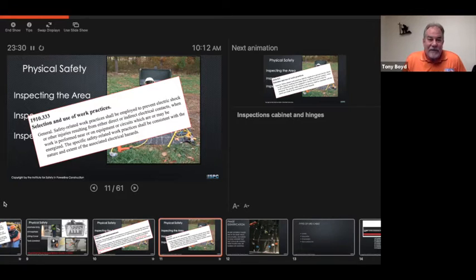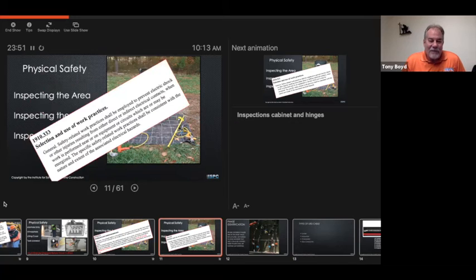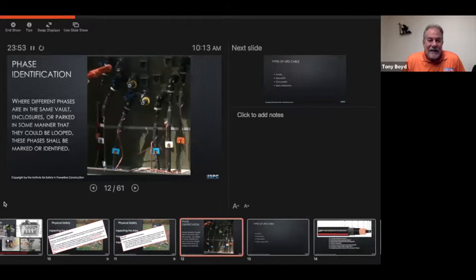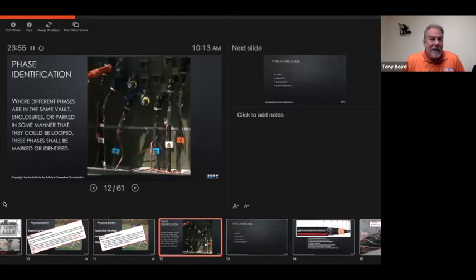I've discovered in the last few years there are slings for actually setting and replacing pad mounted transformers that hold the door open. Back in my days as a young man, we had to rely on somebody that could hold that door open while we were setting and removing the transformer. So just some of those special things that need to be taken into account.